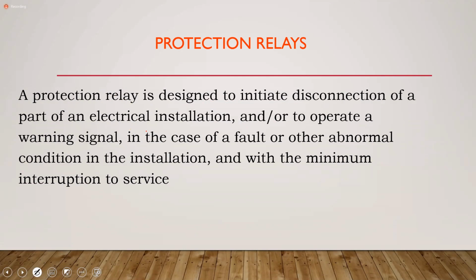That change can also include sending an alarm, because there are some relays in the system whose initial purpose is to alert the utility that there's a problem, or there's a potential problem, or there's a problem on the horizon. Yes?